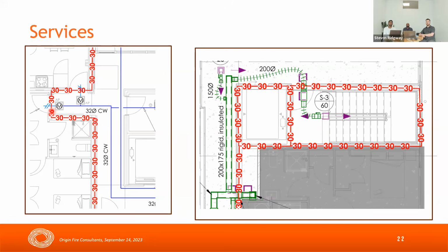So what we do is we collect a list of all the services that are going to be installed in one particular building. If you look at the drawing on the right, you can see that a duct penetrates this fire rated wall, and so we know that we'll need a fire damper installed in this wall. Same here at this end. So we look at the architectural drawing and the services drawing and see where these services penetrate the wall, and then we make a list of all the different situations where we need to provide a fire stop system. Once that's done, we've looked at the fire report, the architectural drawings, and the services drawings. So now we have an idea about what's going on in that building.